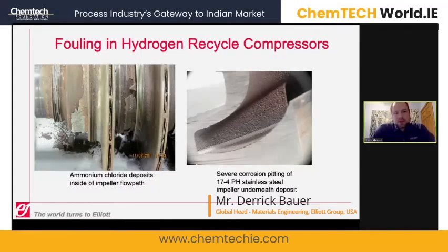One of the major issues is this foulant builds up and it closes up the flow path of the impeller, not allowing the process gas to come through as the design intended. This could lead to lower efficiency and in severe cases, even higher vibration that could lead to a premature shutdown. In the case shown here, the deposit ended up causing corrosion pitting on the surface of the impeller. The impeller was 17-4 PH stainless steel, which has very good corrosion resistance in many environments. However, after cleaning off the ammonium chloride deposits, you can see the pitting of the surface of the impeller.